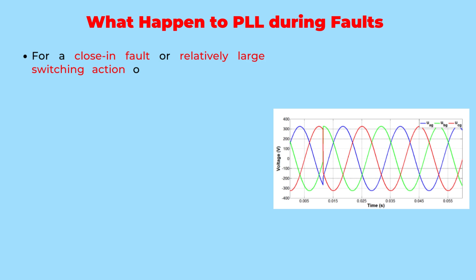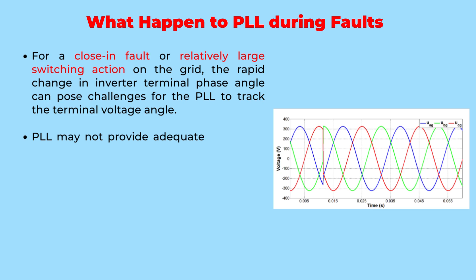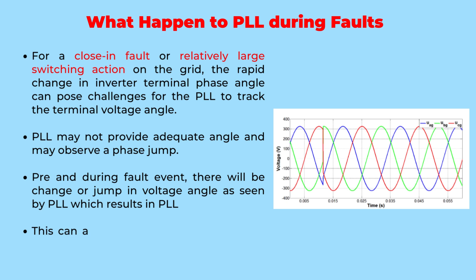Now let us discuss the actual issue of PLL performance during faults. In the dynamic world of power systems, unexpected events can occur that put the performance of the phase-locked loop to the test. During a close-in fault or a significant switching action on the grid, the sudden and drastic change in the inverter's terminal phase angle can present challenges for the PLL's ability to accurately track the voltage angle. The rapid alteration in the inverter's terminal voltage will cause distorted voltage and frequency deviation, and can leave the PLL scrambling to keep up. The PLL, which relies on precise phase measurements to maintain synchronization, may struggle to provide an adequate estimation of the angle as it tries to catch up with the rapidly changing conditions.